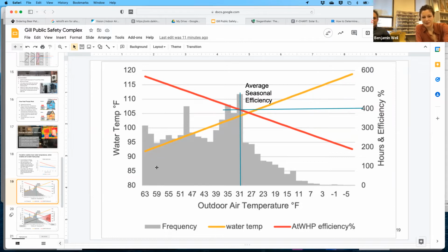And then this yellow line represents the supply water temperature. So as the outdoor air temperature goes down, the supply water temperature that's needed to satisfy heating loads goes up. And these two blue lines, the intersection is the average seasonal efficiency of this heat pump system.